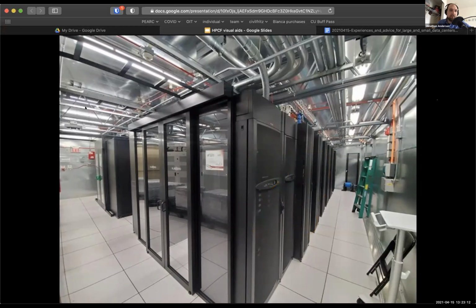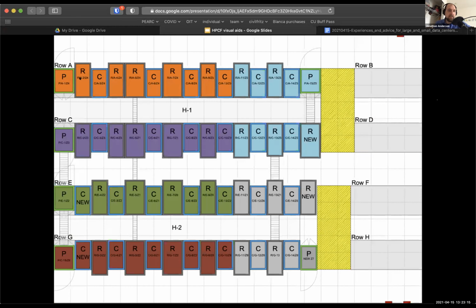We have an interleaving of data center racks with these CRAC or CRAH units. And so we're cooling the air within a confined hot aisle, but nothing direct to the nodes, though we do have pretty good density in how much air we're able to cool. So we're able to put a pretty high thermal load into this environment in our two hot aisle containment pods.